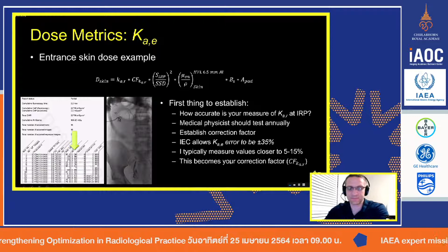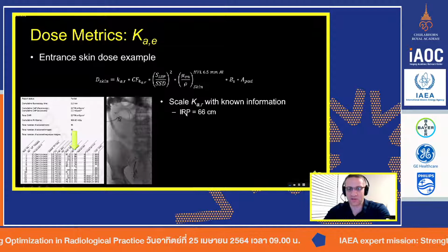We need to scale this, we need to fix this so that the dose at the reference point is actually referring to the dose at the skin entrance level. So in this machine, it's a Philips machine, the international reference point is 66 centimeters from the focal spot. I should have written that there, from the focal spot. The table is actually 97 centimeters. So that's floor to table. And the interesting thing about this, that's important to know, is most table heights are fixed based on the operator. And so you might not always know what the table height is.